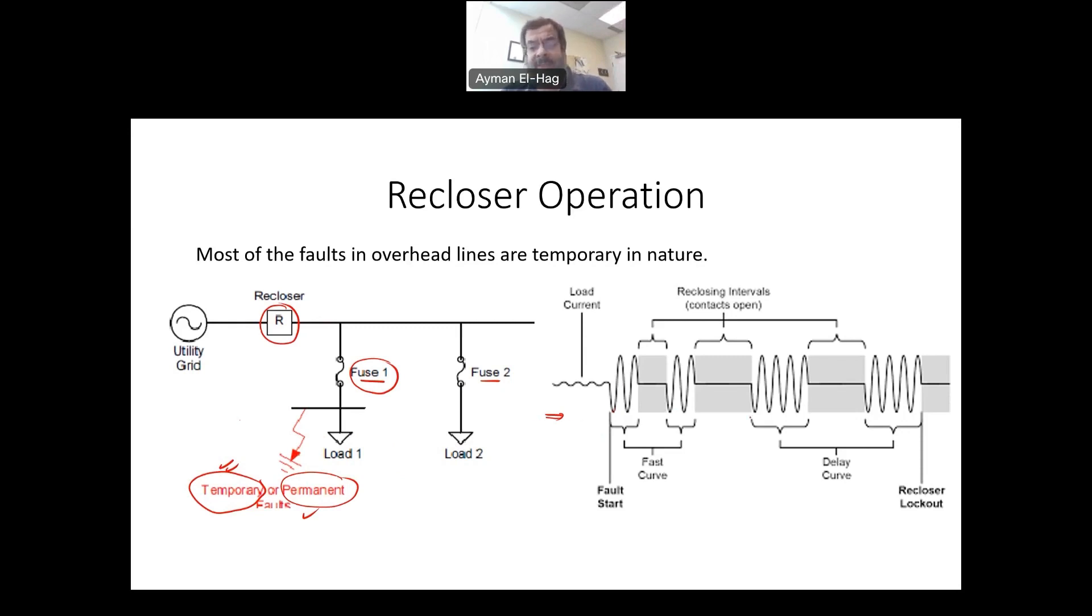if the fault is not cleared, then after that the Recloser will basically re-energize the system but for a longer period. Why doing this? Now it wants to give the fuse the time to melt, the time to clear the fault. So now we are going from the fast to the delay curve stage.